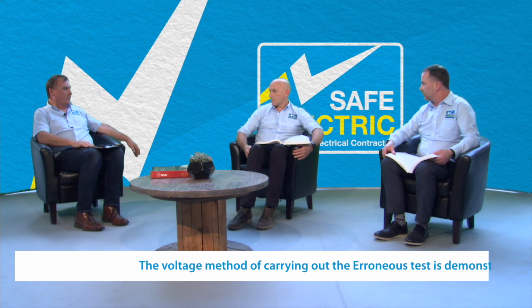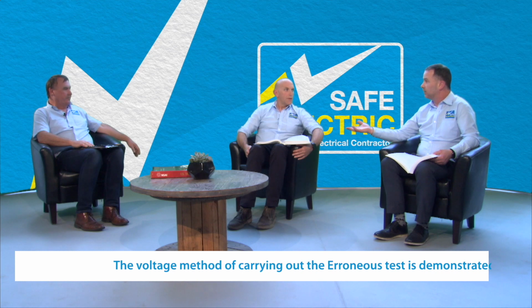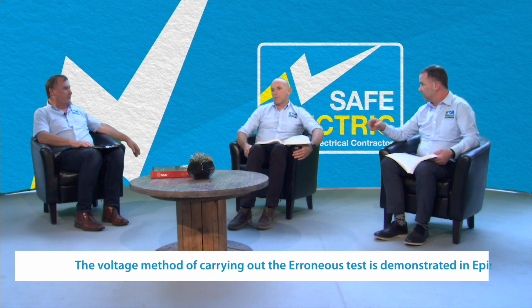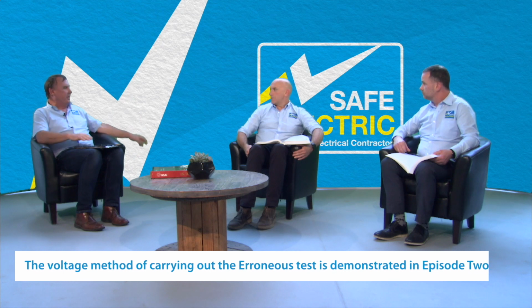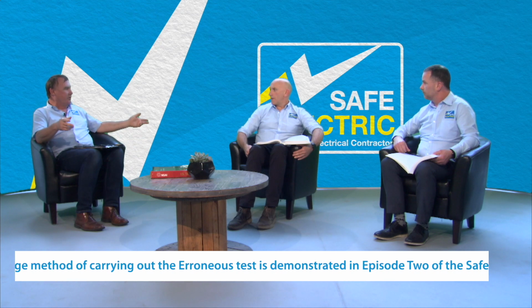There's a risk of damage using the insulation resistance value on an unenergized load. So if we have a fault there, obviously we could drop that voltage across the load. So to do the voltage test, and I suppose Dave's going to tell us how to do it now. But it's very easy to do. It doesn't take very long, and it will give us the results. Again, everything needs to be switched on. We'll demonstrate the test and show everybody how to do it on our test rig.